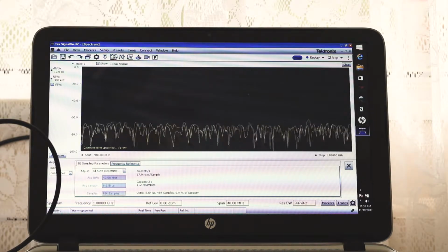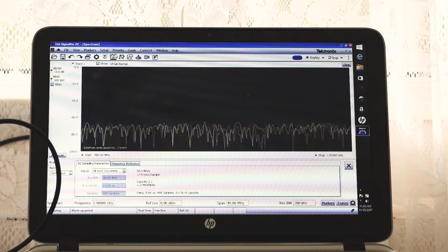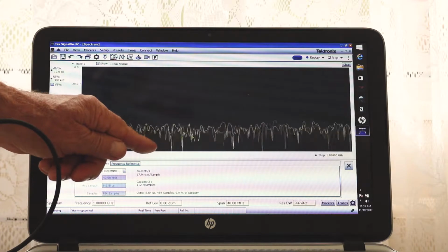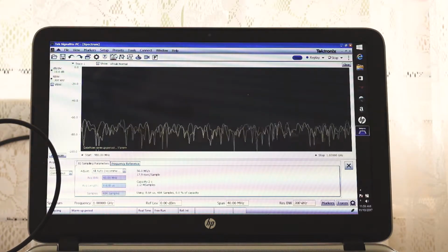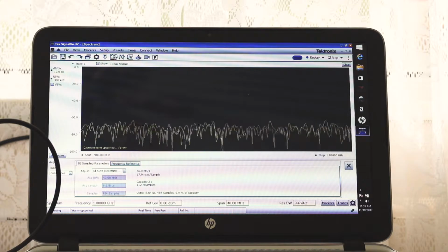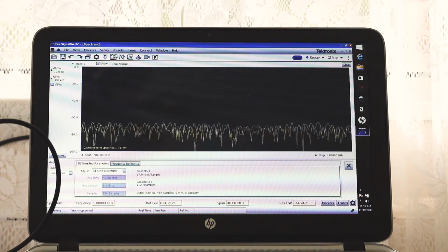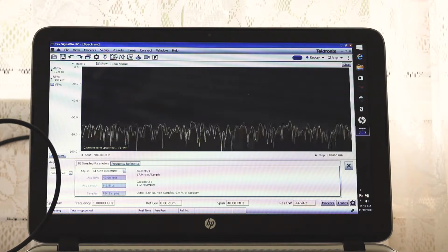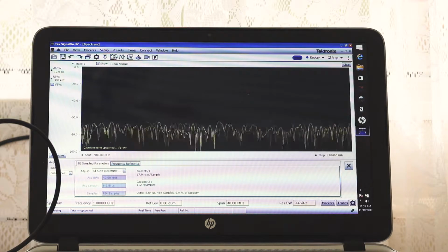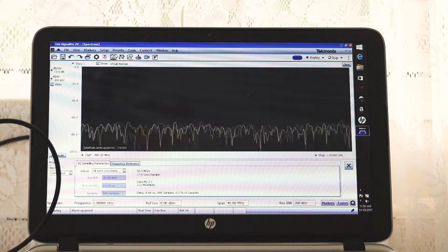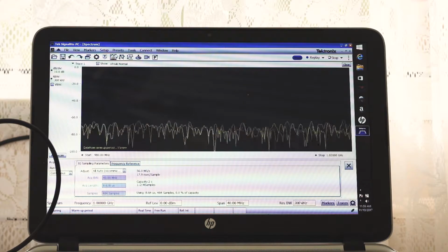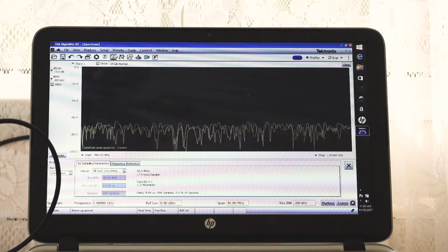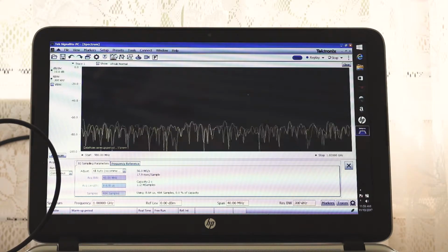In most modulation schemes, signals are filtered to reduce the bandwidth prior to transmission. When the signal under test has passed through a modulation filter, a matching measurement filter should be selected in the instrument in order to interpret symbols properly. The reference filter, while not used for modulation, is important for making proper error vector magnitude measurement calculations. This filter will normally be defined by the modulation-demodulation standard.